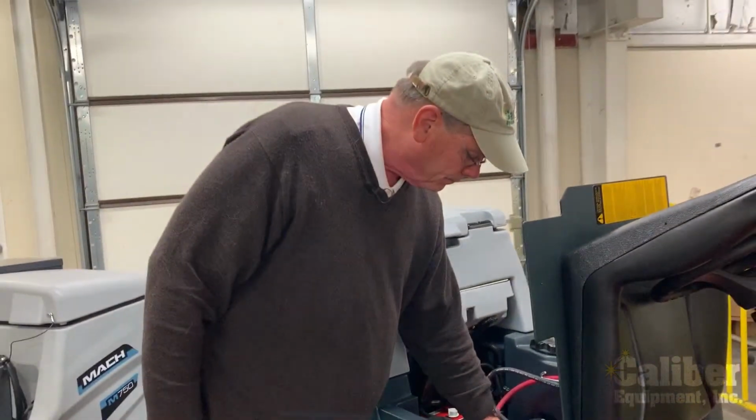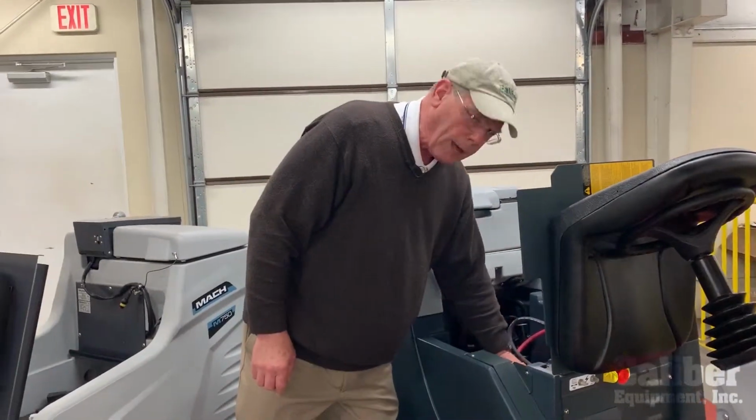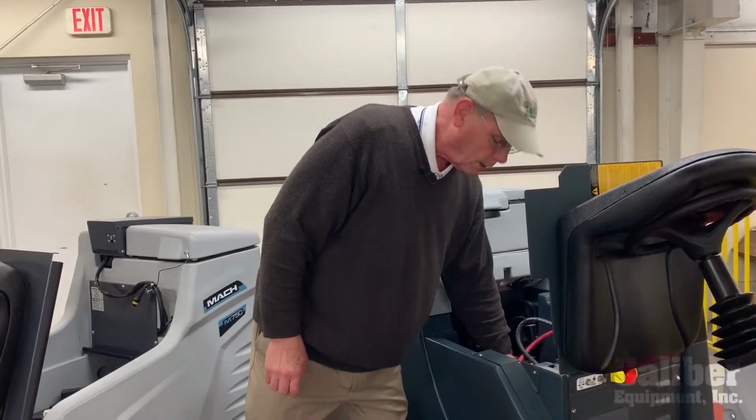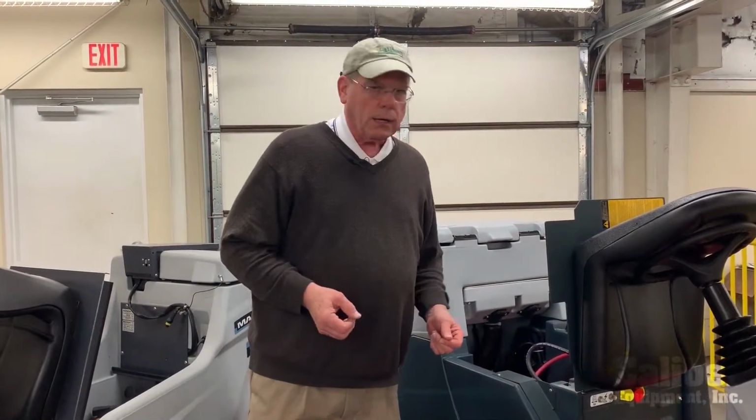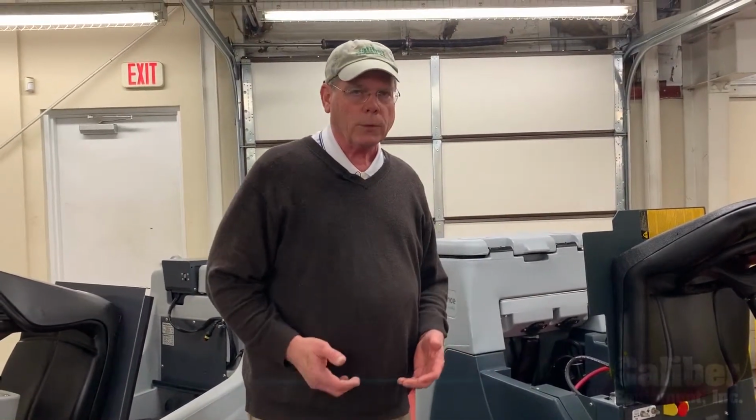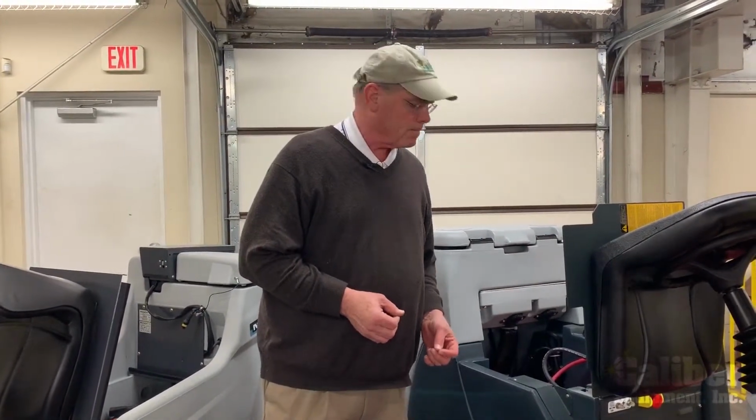Now, the advantage is that when this battery eventually does heat up, it's not going to cause the water to expand outside of the shell of the battery, which is really important, because it's going to be sulfuric acid at this point. When you add water back to the battery, you're blending it in with the sulfuric acid that's in the electrolyte, and we want to contain that electrolyte inside the battery at all times.